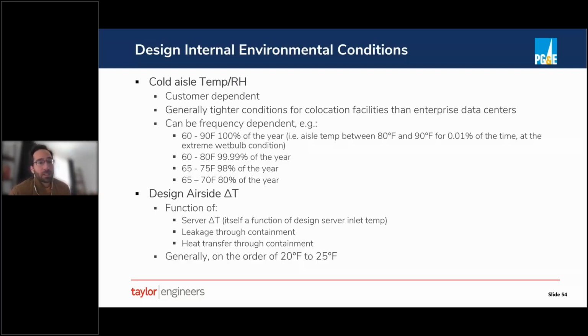Another consideration is the design airside delta T of servers, of the air handling equipment that's serving servers. So you might think that if you know the servers that are going into your facility have an airside delta T, meaning the difference between temperature going in and the temperature leaving, of, say, 20 degrees at your entering server temperature, then that's what you should be selecting your air handlers for. But in reality, the air handlers typically need to be selected for something that's a little bit more conservative than the servers for a couple of reasons.